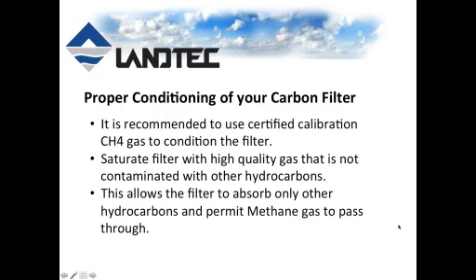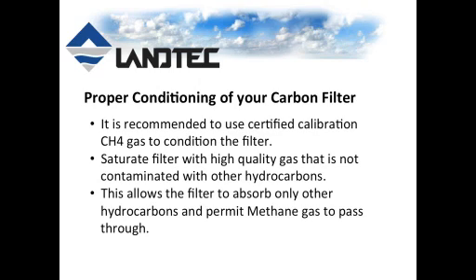A couple of quick notes on properly conditioning your carbon filter. When we go to condition it, it's highly recommended that you use a certified calibration gas — specifically a high purity methane. The reason we do that is we want to saturate the activated carbon media in the filter with a gas that is basically methane and no other hydrocarbons, to the point where it's letting the methane flow through freely. That way, when we go to the field to take a sample, the carbon filter will be absorbing all the other hydrocarbons because we've saturated it with high purity methane.